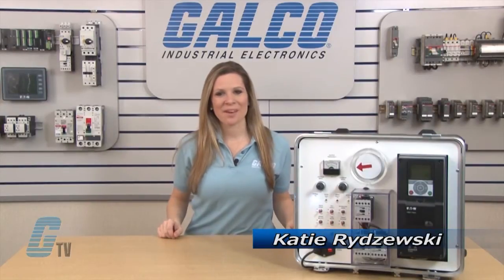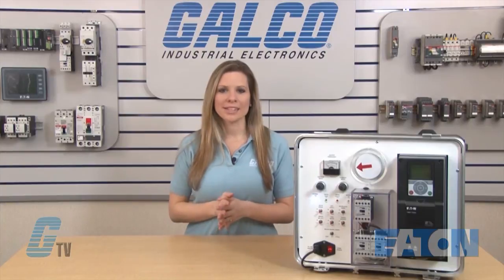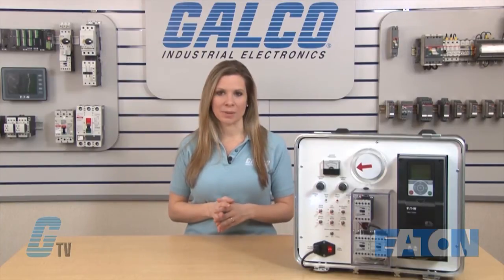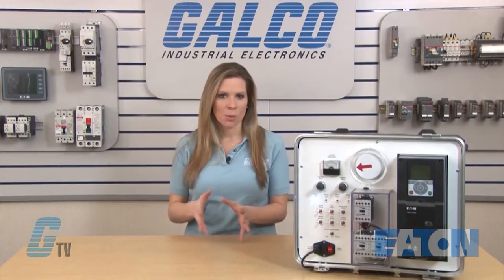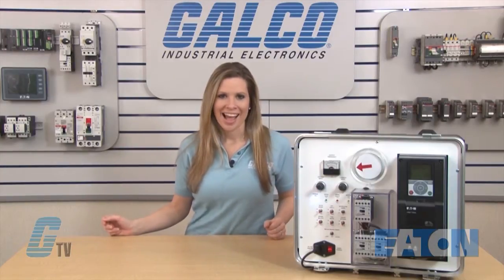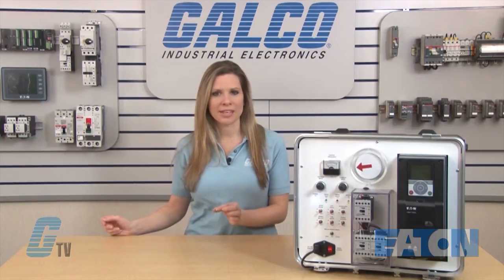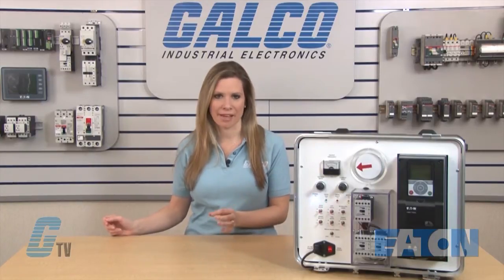Welcome to G-TV! Today I will be showing you PID control on Eaton Cutler Hammer's H-Max HVAC drive. In my scenario, I would like to maintain 75 PSI in a duct with a system capable of 0 to 200 PSI. I will set up this drive for PID control, which will be able to keep my duct pressure at a set level.